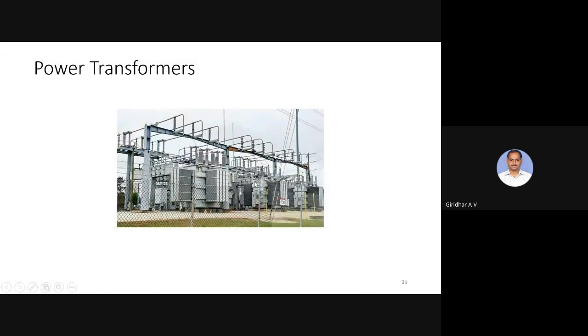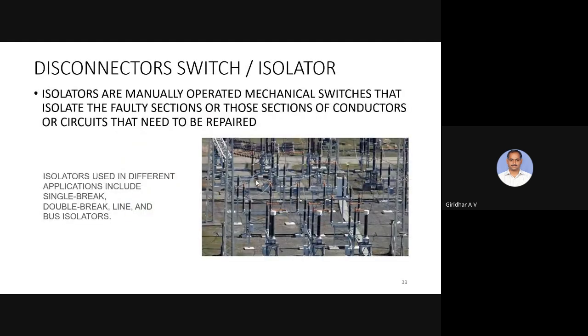So all these aspects you can see here in the outside power transformers. Even in the power transformers nowadays, dissolved gas analyzers are also coming in, where based on the severity of the problems, the content of gas dissolved also can be taken. Even with the sensors and all, the data can be taken and appropriate actions can be taken. Like that, critical, non-critical, all the data can be acquired, whichever is important, whichever is critical, and appropriate communications should be sent. So the SCADA from the master stations will be received very fast, and the appropriate actions will be taken into consideration.